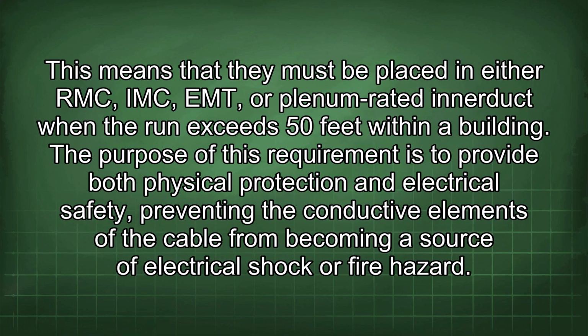This means that they must be placed in either RMC, IMC, or plenum rated innerduct when the run exceeds 50 feet within a building. The purpose of this requirement is to provide both physical protection and electrical safety, preventing the conductive elements of the cable from becoming a source of electrical shock or fire hazard.